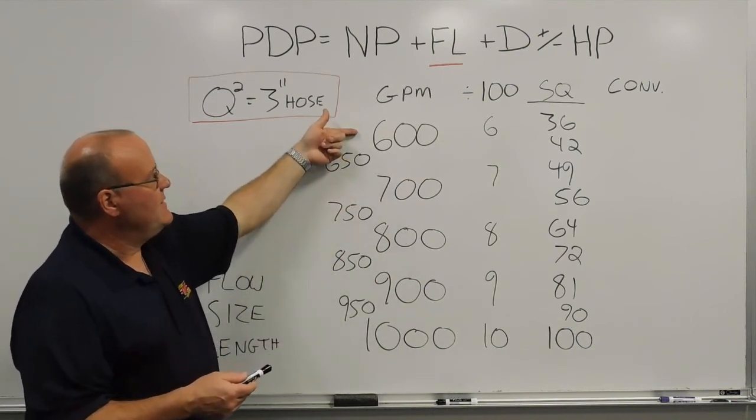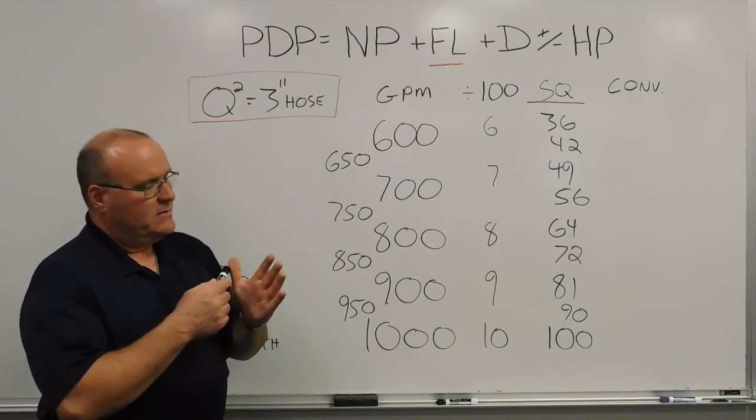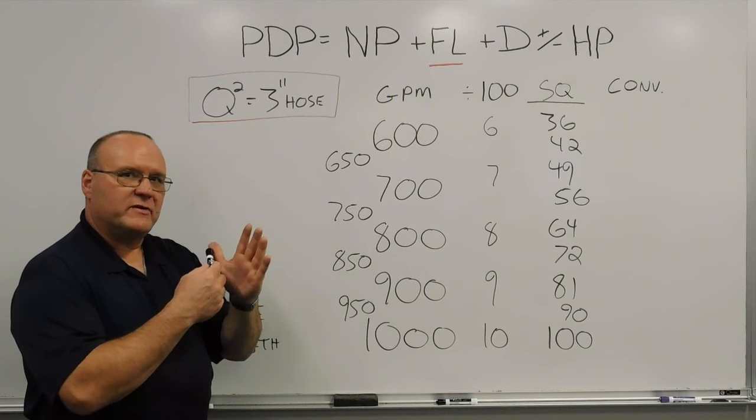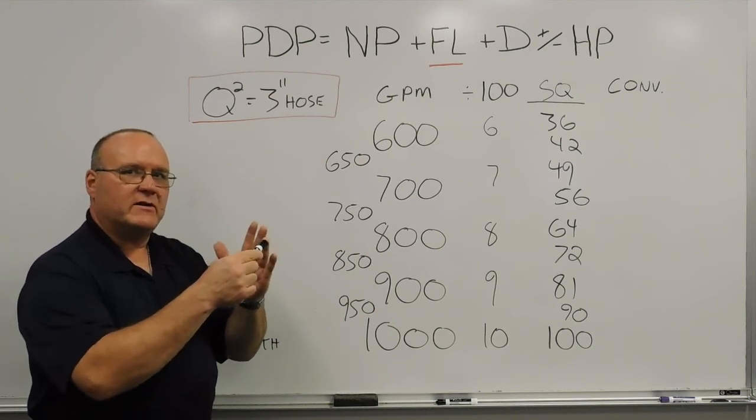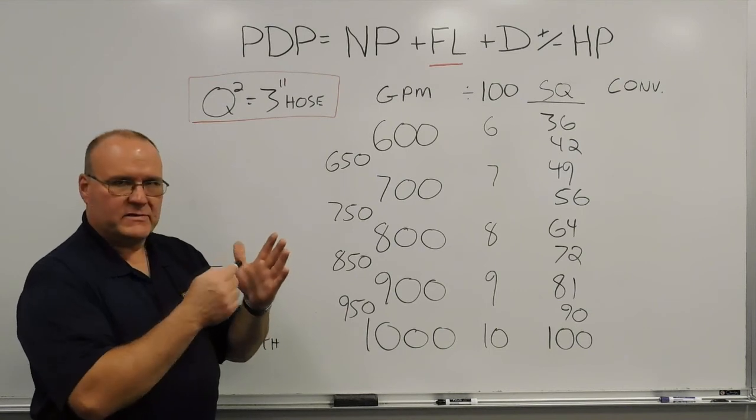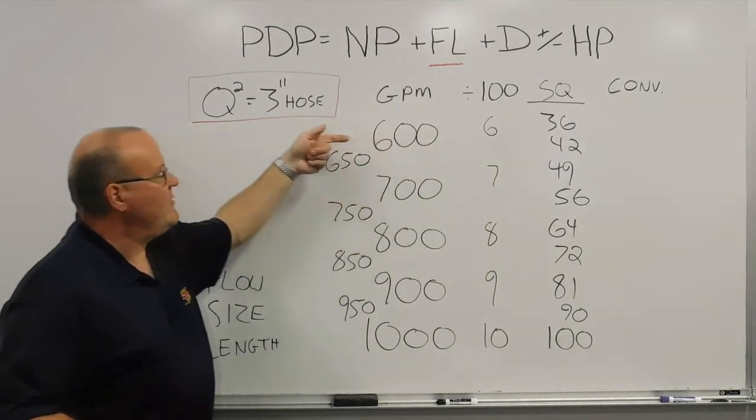So 600 gallons a minute to get to a 3 inch hose number for friction loss, you do the same thing from 600 to 1000, you just add the numbers to the finger, 600, 700, 800, 900 or 1000. So 600 gallons a minute, 6 times 6 would give me 36 pounds of friction loss if that were 3 inch hose.